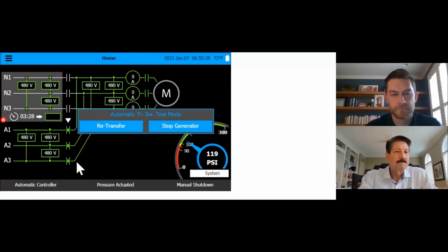And then on the flip side, before it transfers over, there's a slight delay once it meets that criteria, as I mentioned to you. So again, it's timing out. In this particular case, it knows it's a test. As long as we have stability for 5 minutes on the normal side, it will retransfer back and let the genset cool down for a period of time, whatever the timer might be on the genset itself. I think on our screen, it'll only run 5 minutes. And once that expires, it will cut the signal off. And then if there's a timer that overrides on the genset, it might run another 25 minutes or whatever that might be. So what I'm going to do is retransfer here.